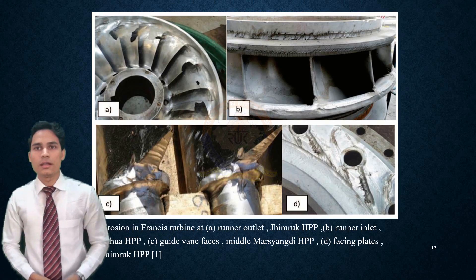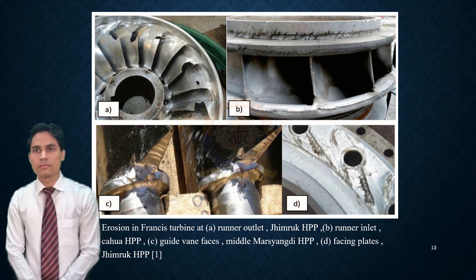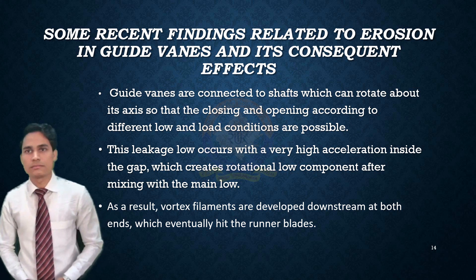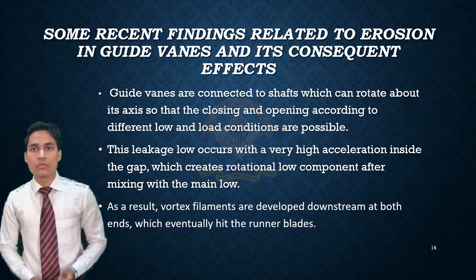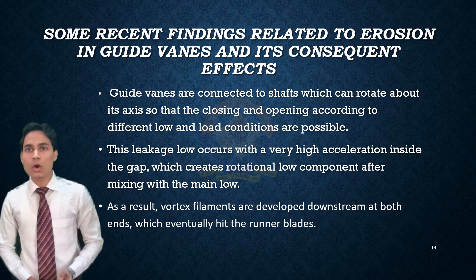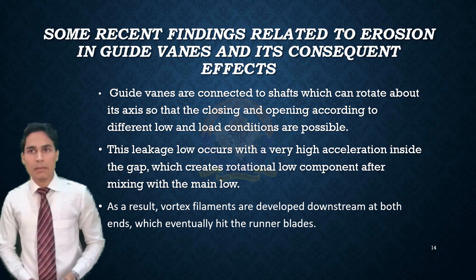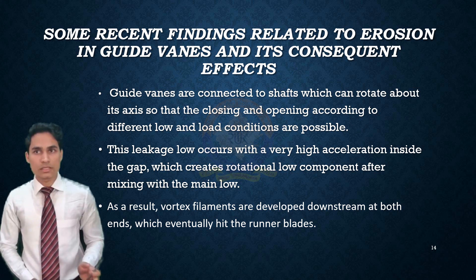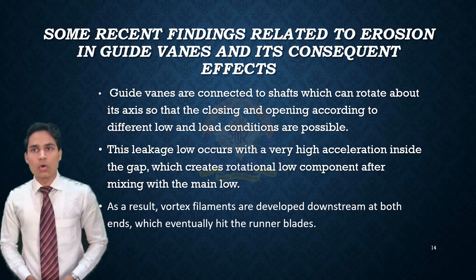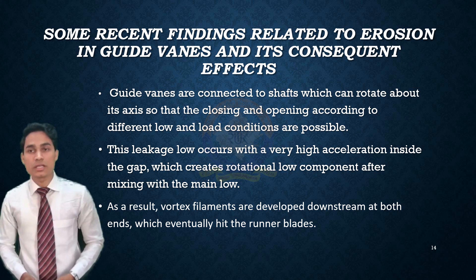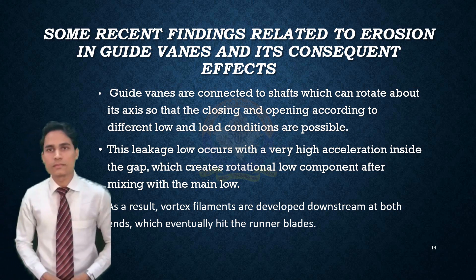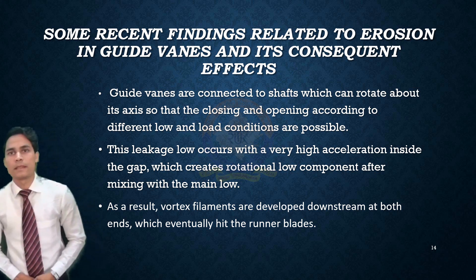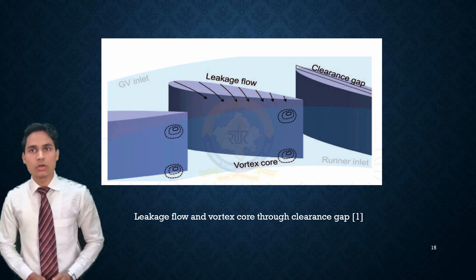Some recent findings related to erosion in guide vanes and its consequent effects. Guide vanes are connected to shafts which can rotate about their axis so that closing and opening according to different flow and load conditions are possible. Inside the clearance gap, the flow is driven from the high pressure side to the low pressure side, disturbing the primary flow. This leakage occurs with very high acceleration inside the gap, which creates a rotational flow component after mixing with the main flow. As a result, vortex filament elements are developed downstream at both ends, which eventually hit the runner blades.